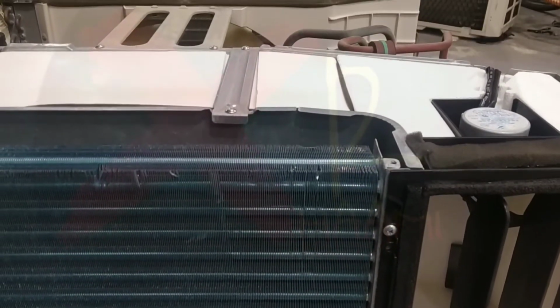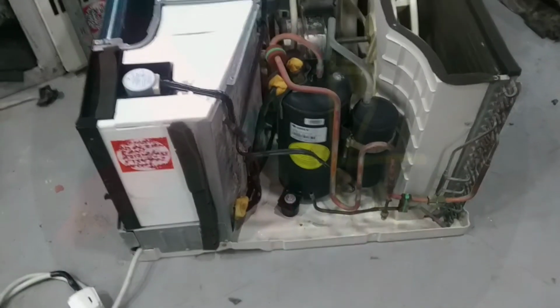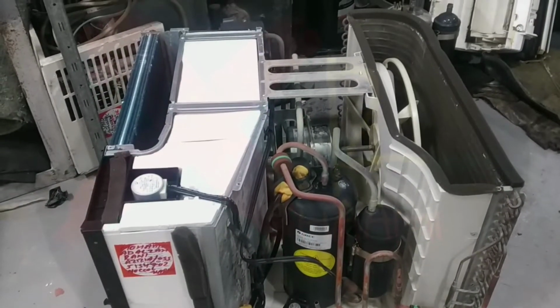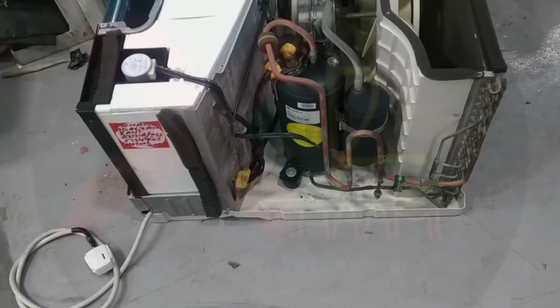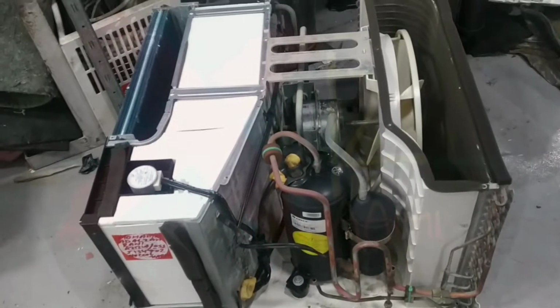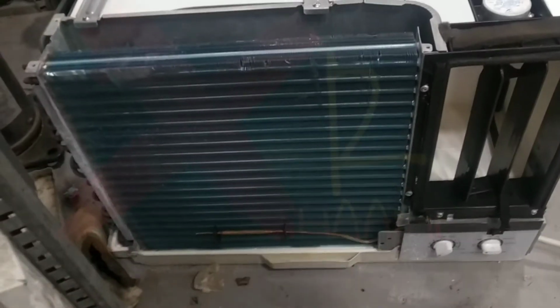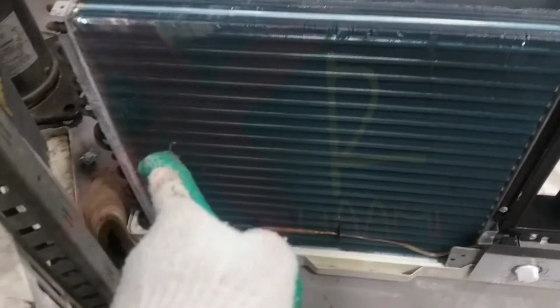In this video we're going to talk about the icing over problem in our air conditioner. There are many reasons why your AC unit may be freezing up. First of all, you have to open the front panel and check the cooling coil for icing over. You can see this is the cooling coil, and sometimes here you can see the icing. Most of the time you can see the icing on the bends of the cooling coil or evaporator coil.